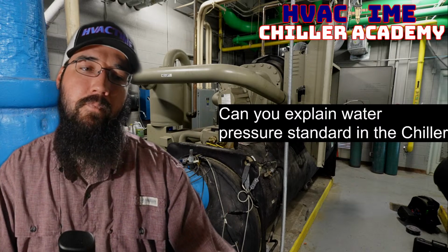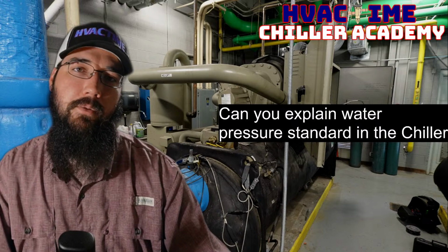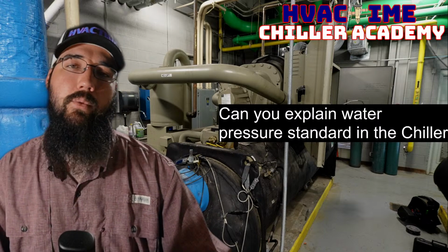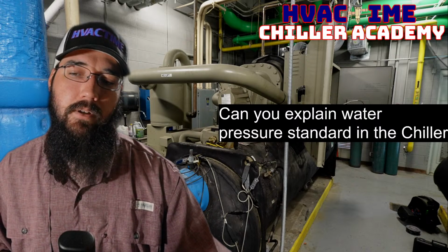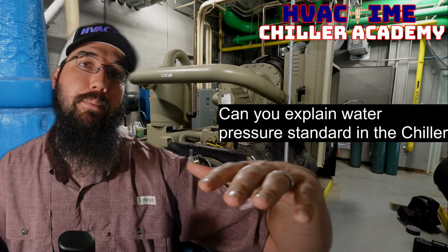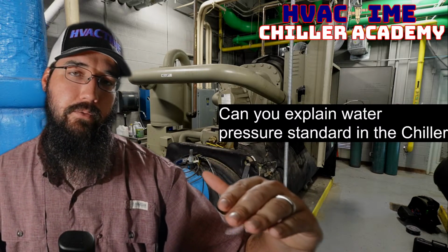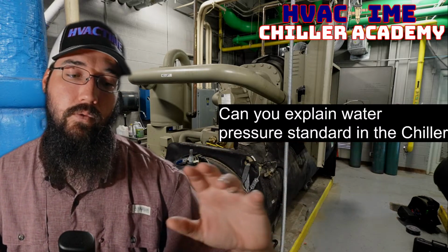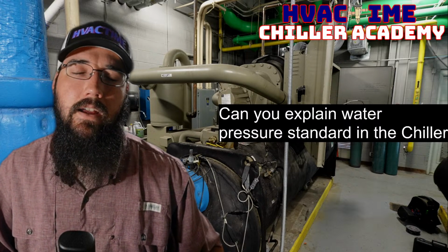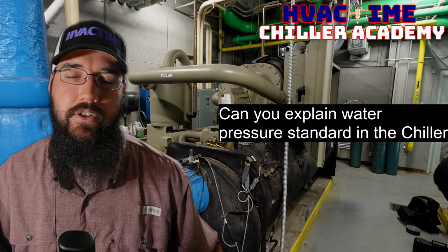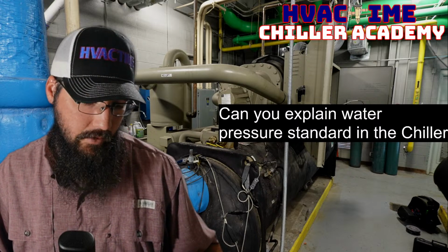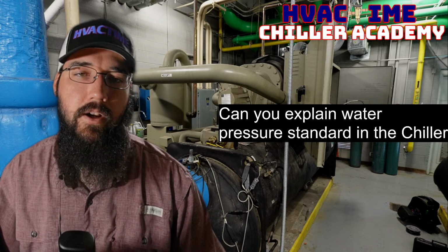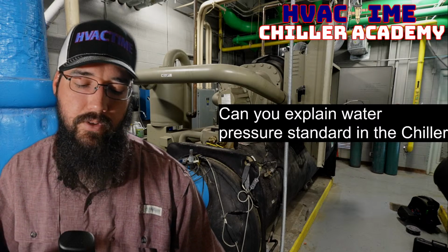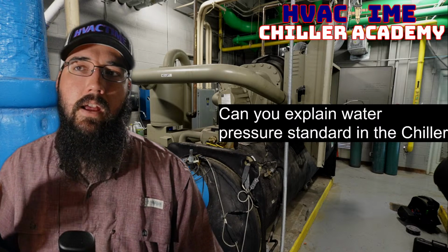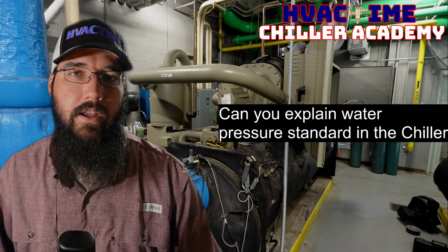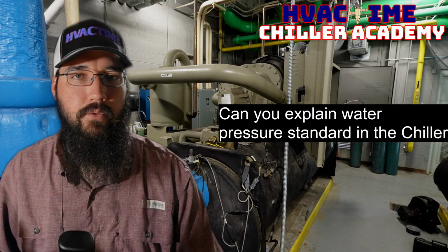Whereas with a closed loop, other than the bladder tank, there's not as much breathing space, so we can actually make that water begin to cavitate if we do not keep enough pressure at the top of the loop, which is where I recommend that 8 to 10 psi on a closed loop application. So yeah, either direction you were going to go with that question, I hope that helps. And it's a very important topic that I really see a lot of people struggle with. Understandably so. It's not explained well enough, in my opinion, throughout the industry.